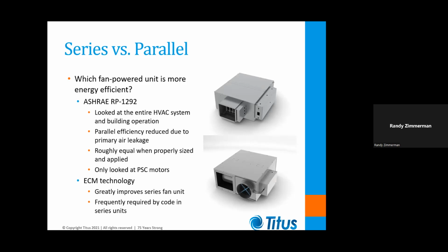The answer was, it depends. If you properly size and select these boxes, you could get equal results with a both series or parallel unit. Now, unfortunately, when this project was conceived, most fan-powered units were using PSC fan motors. Those are permanent split capacitor fan motors.